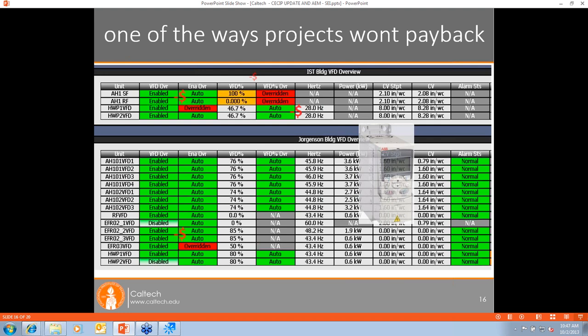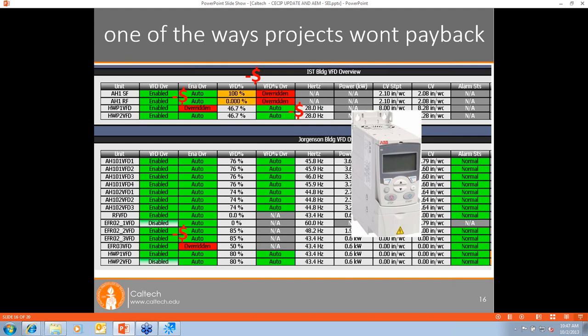And that's a question for anybody on the webinar today to take back to their plant operating folks. You know, it's just a simple question. What are we doing to maximize delta T on our campus? And that's a takeaway we have for you here today. There's a lot of power in pumping and chiller energy that can be recovered if you try to maximize your delta T. So we'll leave it at that in the interest of time, but maybe write that one down if you're taking a few notes today. This one is not necessarily that hard to achieve and go for.